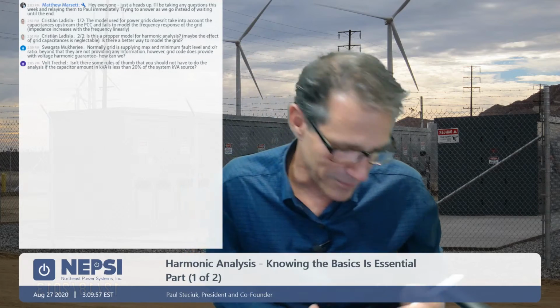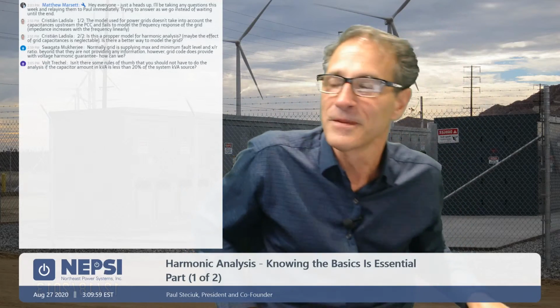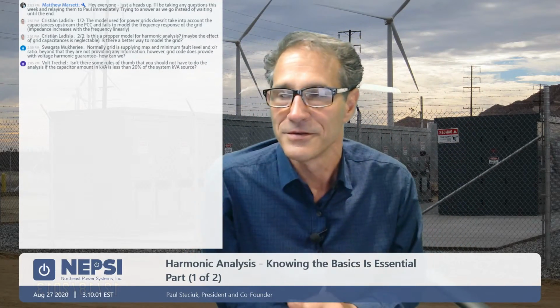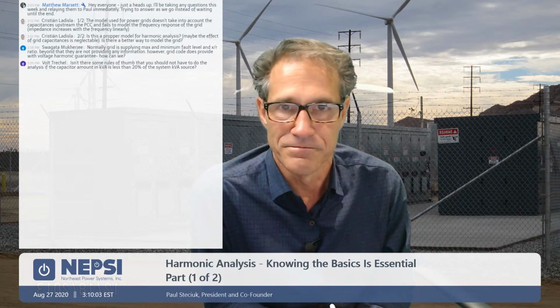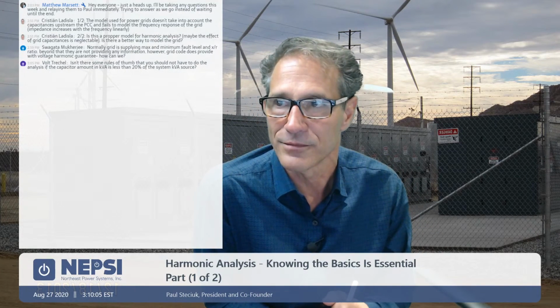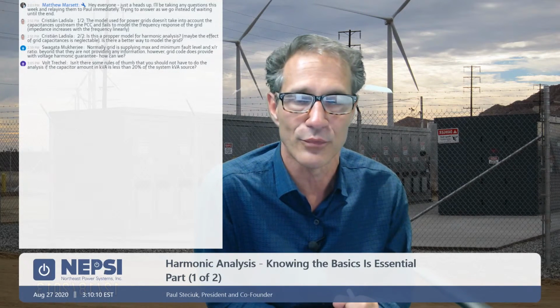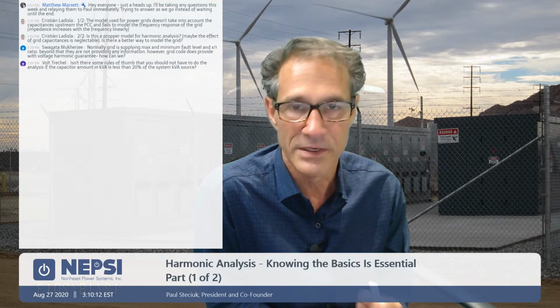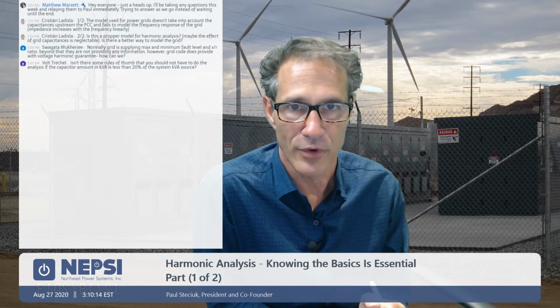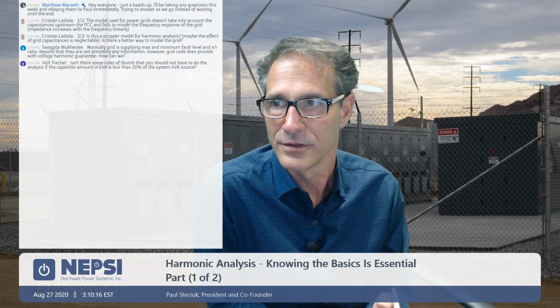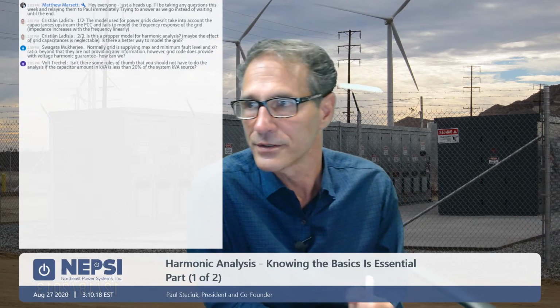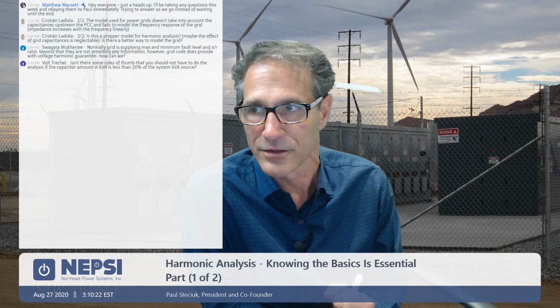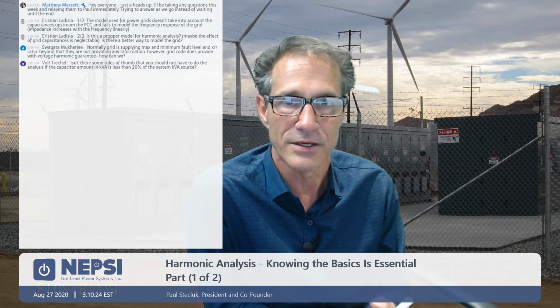This is exactly what I was talking about. The rules of thumb. There is no basis for those rules of thumb. I can easily show you that this 20% rule does not work. If you have resonance, you've got a problem. It has nothing to do with a percent of load. I've been seeing this, and this is really something produced by the low voltage guys.